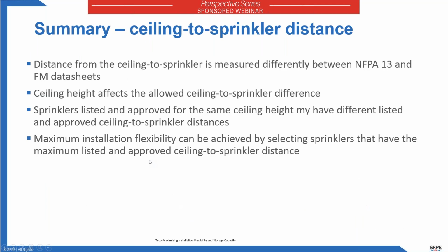So in summary, the distance from the ceiling to the sprinkler is measured differently between NFPA 13 and the FM data sheets. And so it's important to understand which requirement you're using and be sure that you're measuring the sprinkler appropriately. Ceiling heights affect the allowed ceiling to sprinkler distance. Sprinklers listed and approved for the same ceiling height may have different listed and approved ceiling to sprinkler distances. And the maximum installation flexibility can be achieved by selecting sprinklers that have the maximum listed and approved ceiling to sprinkler distance.